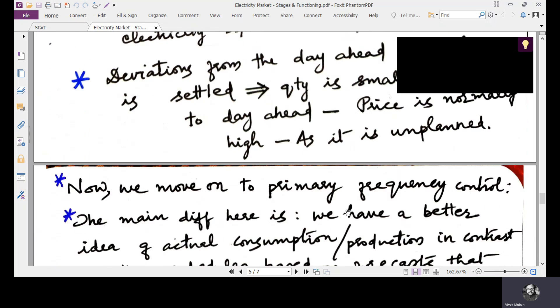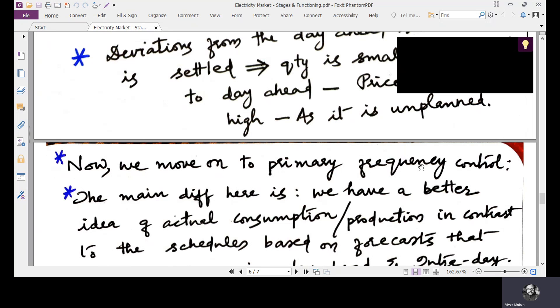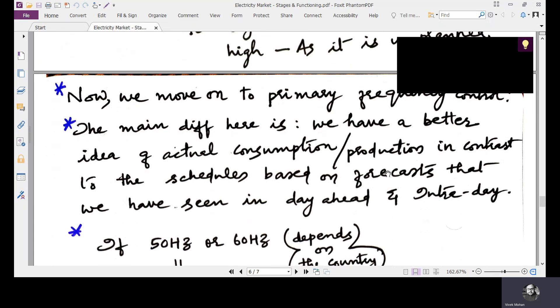After the intraday market, we move on to a shorter timeframe where primary frequency control is done. The key difference here is that we have a better idea of actual consumption and production compared to the forecast-based schedules used in the day ahead market. Primary frequency control happens within 30 seconds — generators must activate it within 30 seconds and it can last up to 5 minutes, so it must be immediately available.